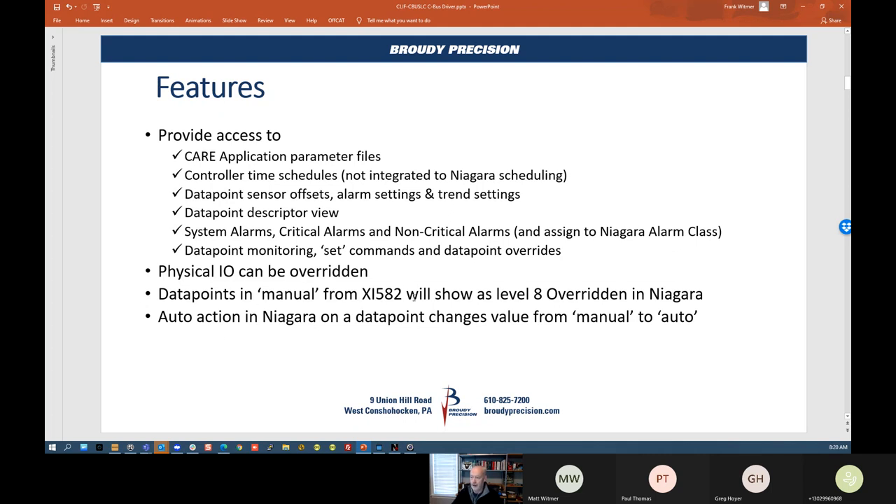When data points are in manual from an XI 582, they'll show up in Niagara as level eight overridden. With previous drivers, if you put a point in manual from the CBUS side using your XI 582, there was no way to take them out of manual from the Niagara side — you had to go back on the CBUS side with the XI582 or your laptop to take it out of manual. Somebody could go in there and do that and we'd be stuck with no remote control at that point.